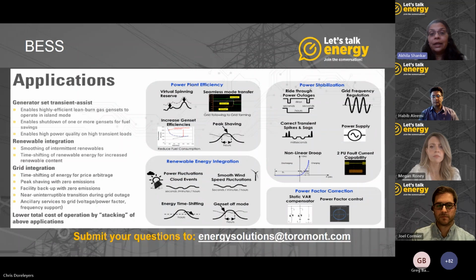Now, when a genset takes on load, it results in transient voltage and frequency dips, which means poor power quality to the loads. When a battery energy storage system is used in combination with the generator set, the energy from the batteries can be used so that one or more generators can be shut down. And when used in combination with the genset, the energy from the batteries reduces the transient voltage dips and frequency dips, and it improves the power quality to the loads.